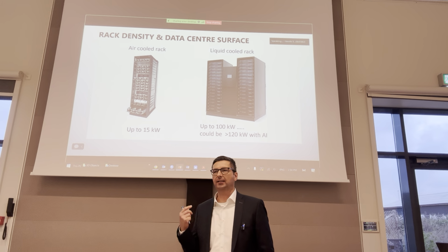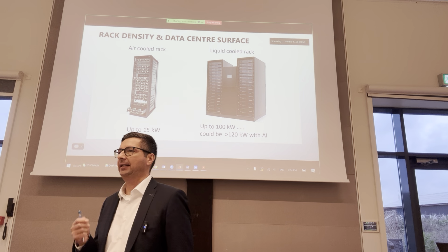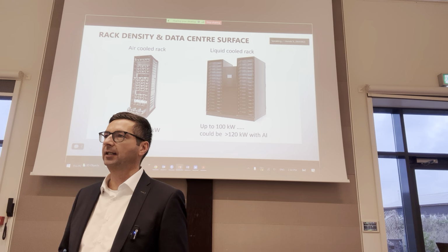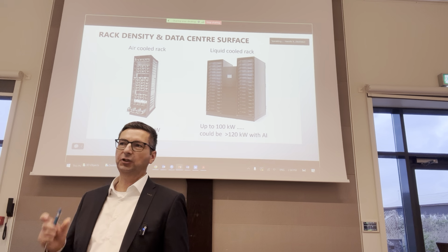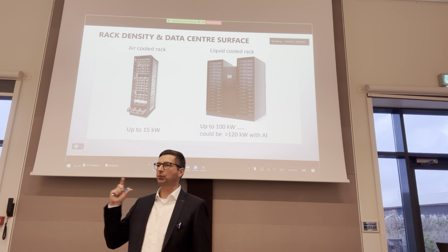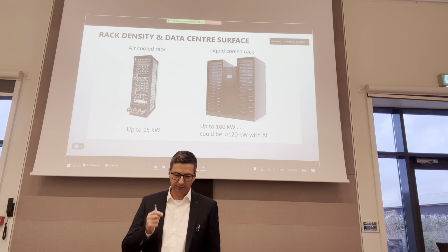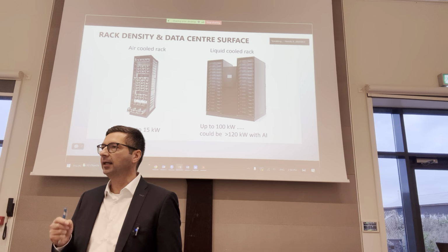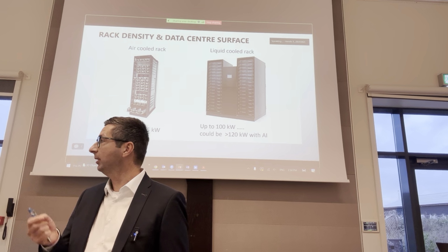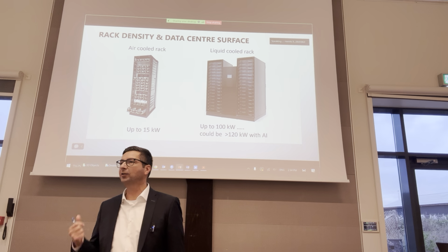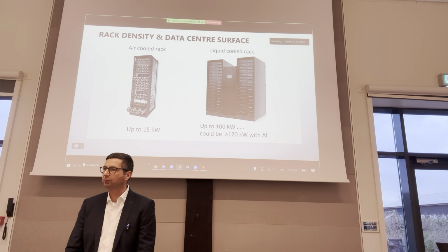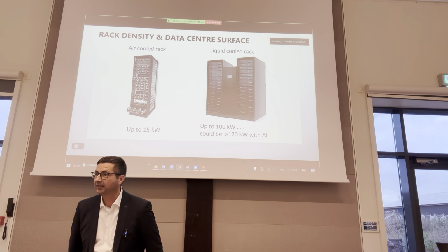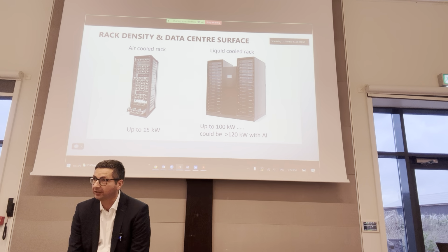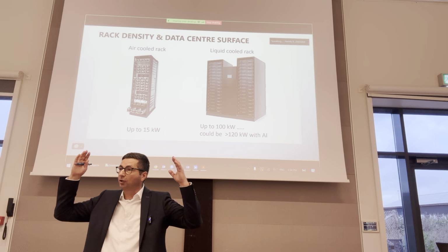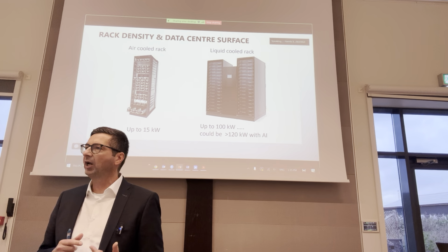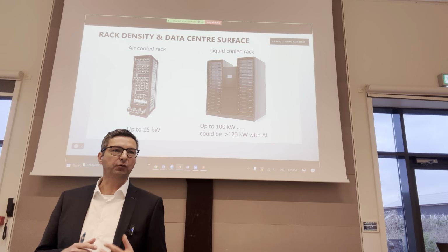So basically, liquid cooling as such. If you look at this slide, really comparing a legacy traditional air-cooled rack with a liquid-cooled rack, and we're just looking at the space needed in comparison to those two setups, the space needed per IT capacity, kilo per kilowatt. If you look at the old legacy one, you need space in the front for the cool aisle, in the back for the hot aisle, at the bottom for the raised floor, and on the top for the ceiling. Altogether per rack, you need 15 cubic meters of space.